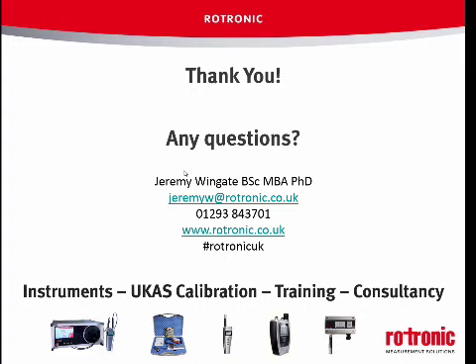Okay, we go from London now to Canada, and this is a question from David. David asks, what do you recommend as a time period between calibrations? It's a classic question. It really depends on the application. We're often not allowed to say when things can be calibrated because it depends on your application. As an example, in the pharmaceutical industry, in a very important environment, maybe a production area, they may check the sensors every 3 months and do a proper calibration every 6 months, maybe do an accredited calibration every year. Now that's fairly extreme and there's a lot of money behind that.